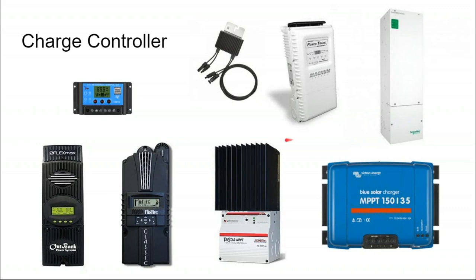You also have to watch out for the voltage levels of charge controllers, because many of them are only rated for 150 or 300 volts on the solar input. That can surprise a lot of solar installers because they're used to installing 600 volt circuits. When you get into 300 volt circuit design instead of 600 volt for the same amount of power, you have half the voltage and twice the amperage, so you get into shorter circuits and numerous circuits. So I select a 600 volt charge controller to go with a 600 volt solar array so that I can minimize the number of circuits.